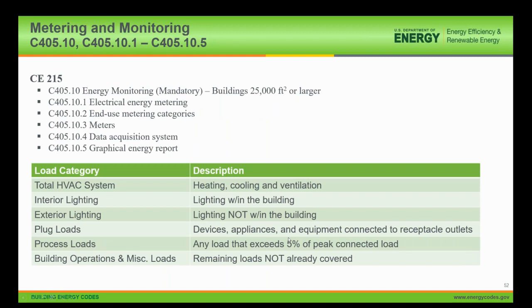A larger change involves metering and monitoring, with the introduction of C405.10, which is energy monitoring, and it's mandatory in buildings that are 25,000 square feet or larger. It outlines a number of provisions, one being electrical energy metering, and it defines what the end use metering categories are, shown down below.